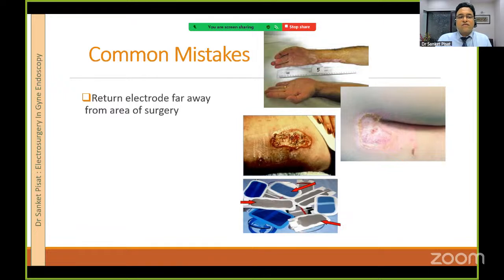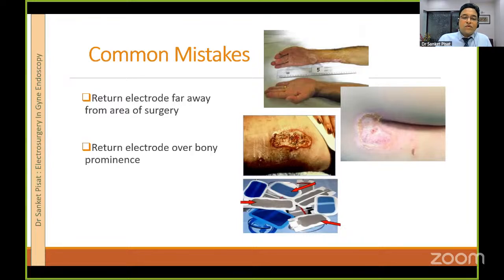Applying a return electrode far away from the area of the surgery. You are forcing current to go through a wider path of tissue when it is actually not required. Applying the return electrode over a bony prominence. Traditionally we have been taught to apply return electrodes over the buttocks, over the thighs, or padded areas from where the current will have an additional buffer of subcutaneous tissue or muscle when it escapes.